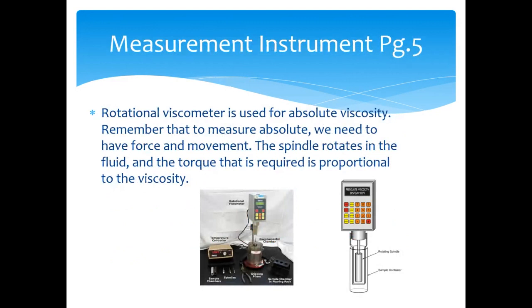For measuring absolute or dynamic viscosity, we use the rotational viscometer. To measure absolute viscosity we need force and movement, so the rotational viscometer has a spindle that rotates in the fluid, and the torque required to keep that spindle turning is proportional to the viscosity of that fluid.